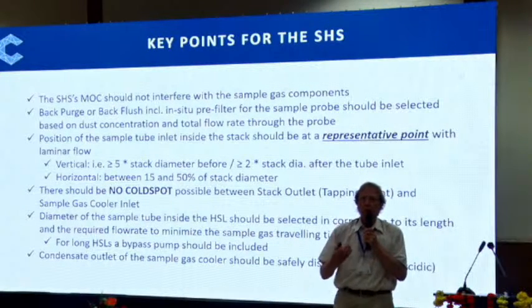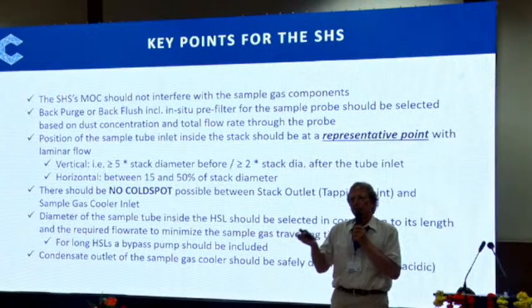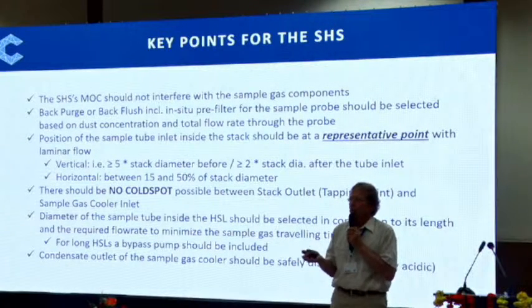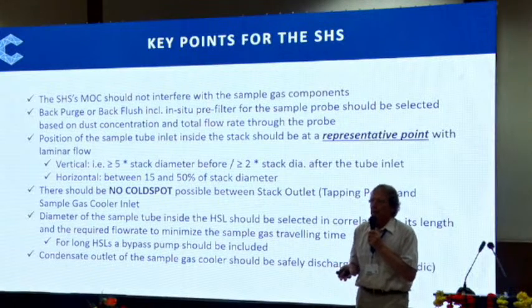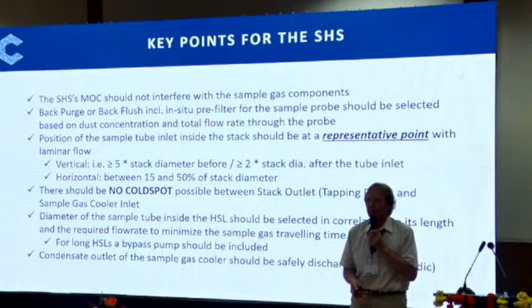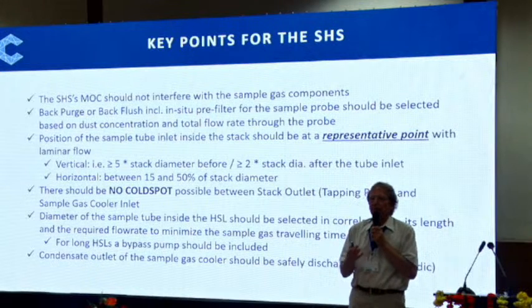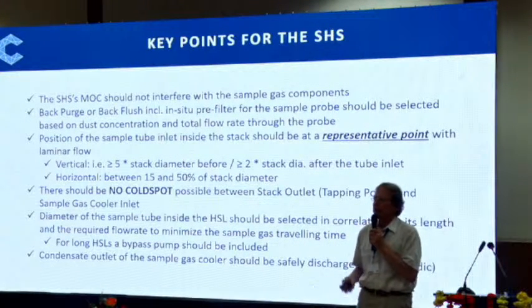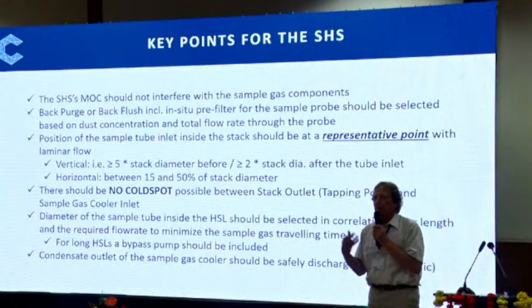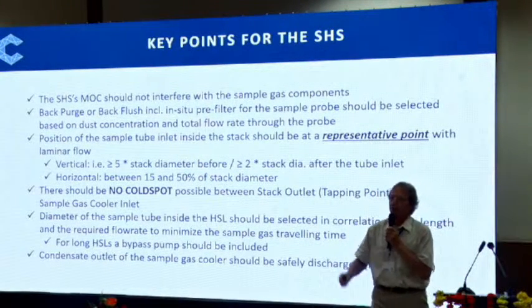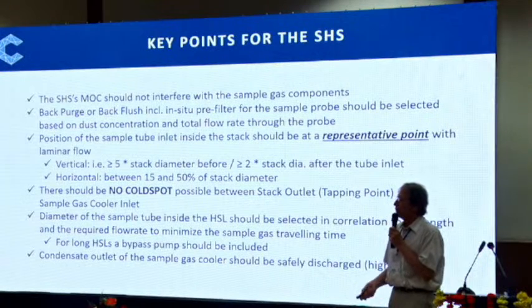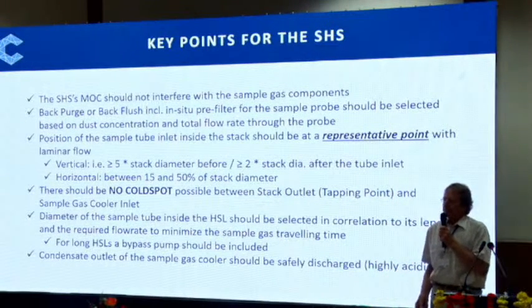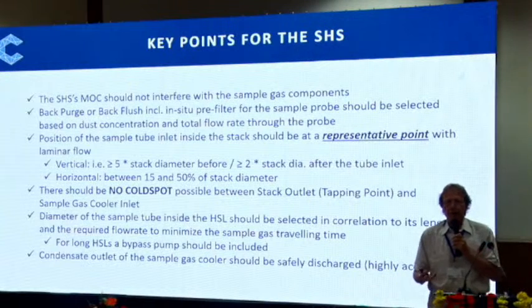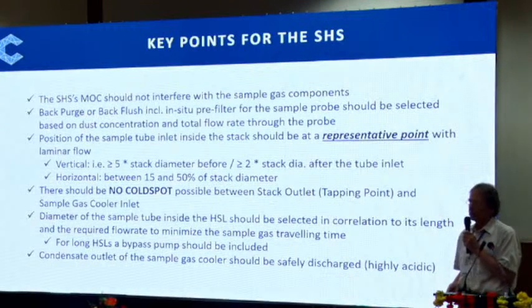Because if you take too low a flow, you're creating a differential pressure. If you use a 1/4 inch or 6 mm tube and you have a 50, 60, 100 meter umbilical, you're creating a significant differential pressure, and your sample gas pump might not even be able to cope with it. So you're not getting enough gas through. So use a bypass pump and go to a larger diameter, 3/8 inch or 12 mm or whatever, in order to reduce the traveling time through the umbilical.